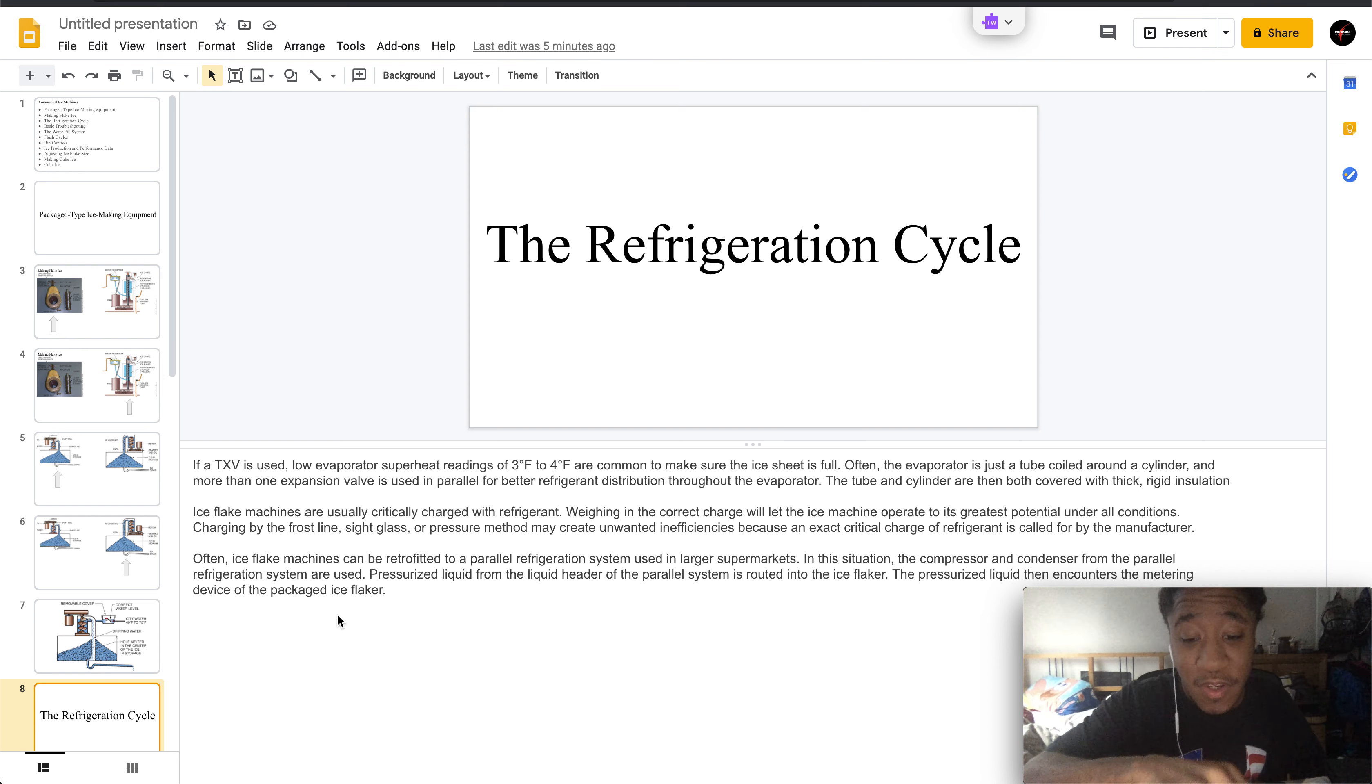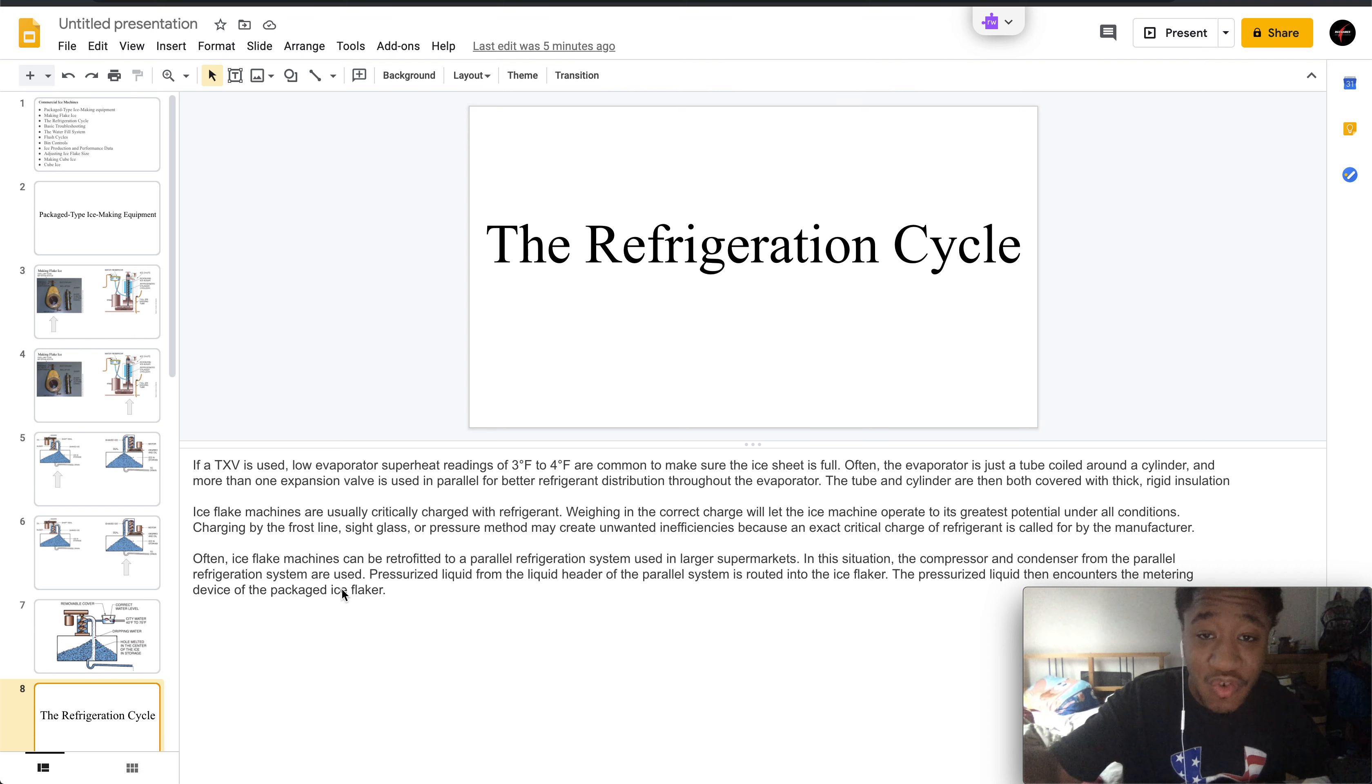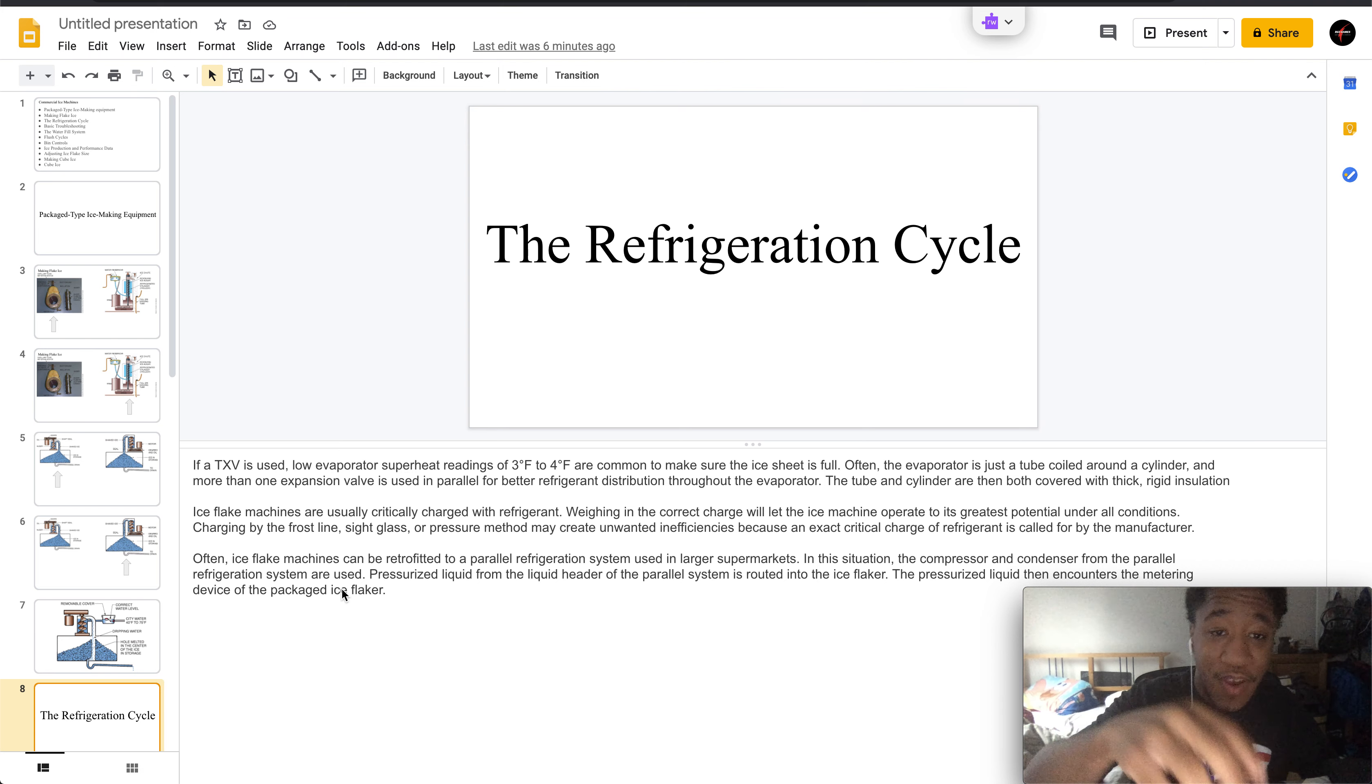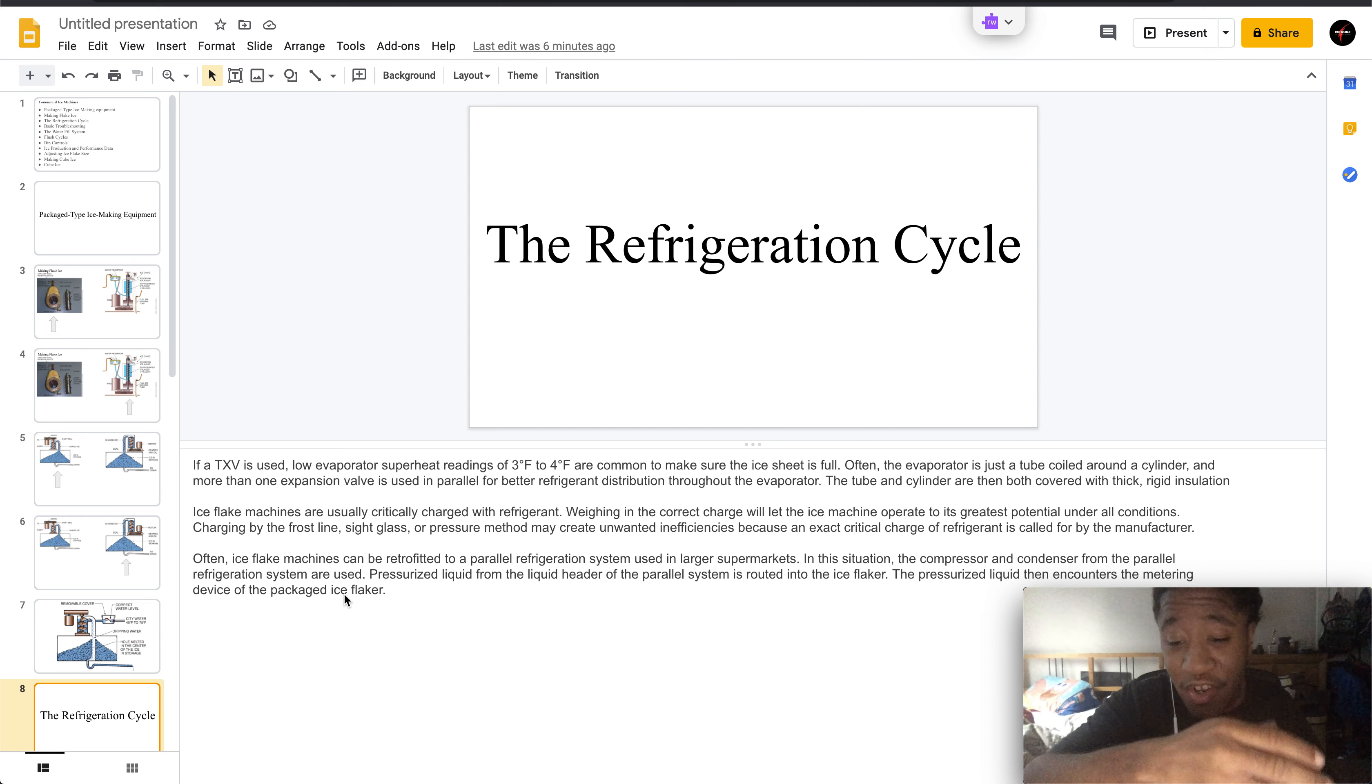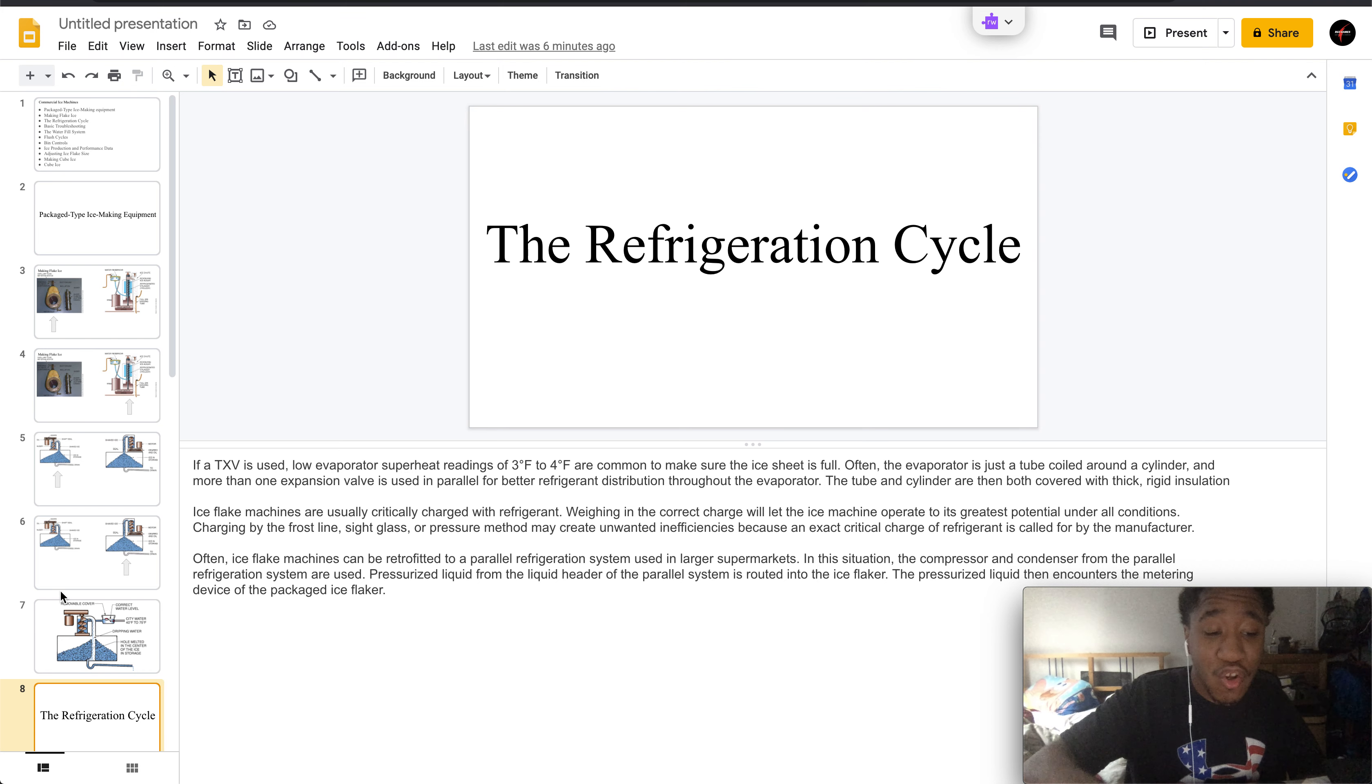This is because an exact critical charge of refrigerant is needed by the manufacturer. Ice flake machines are often retrofitted to a parallel refrigeration system used in large supermarkets. In this situation, the compressor and condenser from the parallel refrigeration system are used, and the pressurized liquid from the head of the parallel system is routed to the ice flaker. The pressurized liquid will encounter the metering device of the packaged flaker.